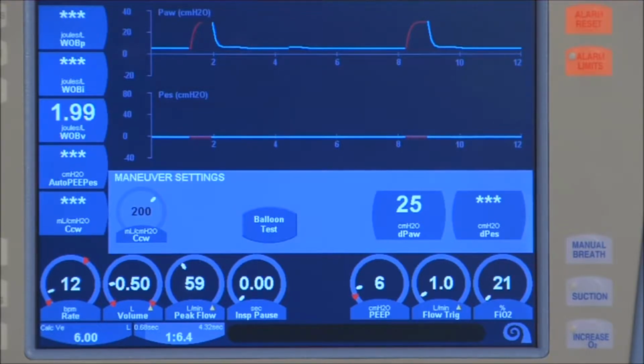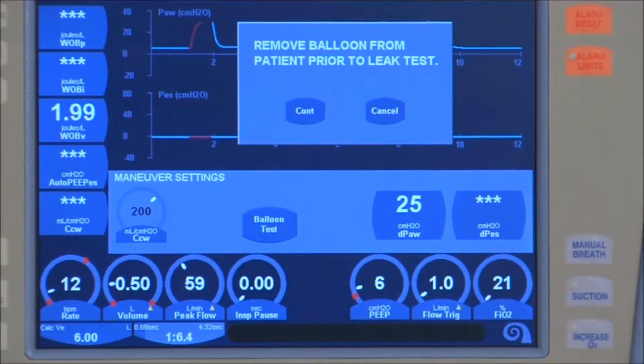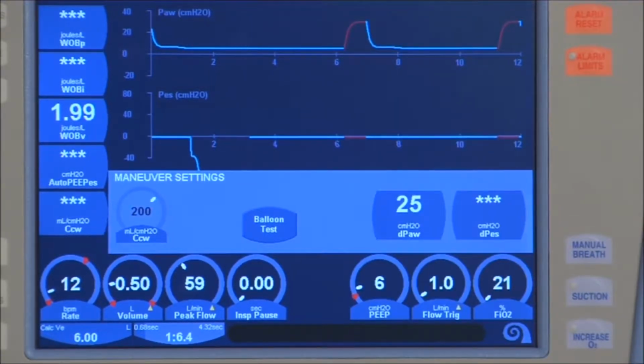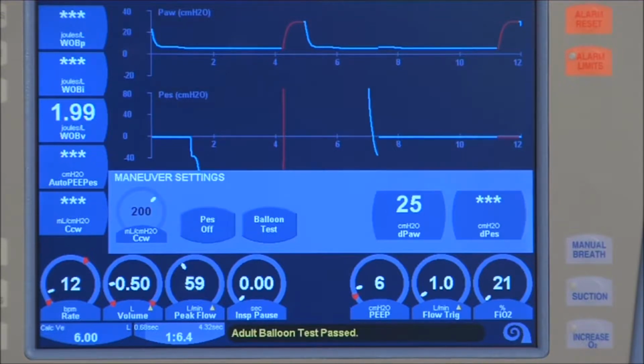The ventilator will then advise the operator to be sure the catheter is removed from the patient. Depress the button and allow 10 seconds for the balloon test to be conducted. Once the balloon test is completed, a message of Balloon Test Passed will be displayed on the bottom of the screen. The balloon is now ready for insertion.